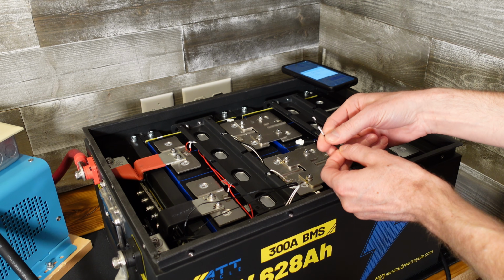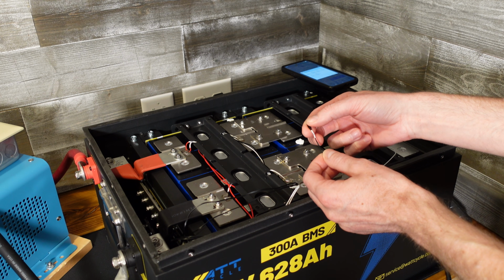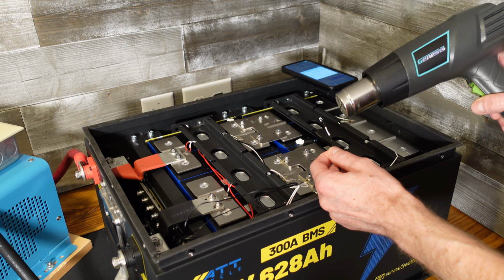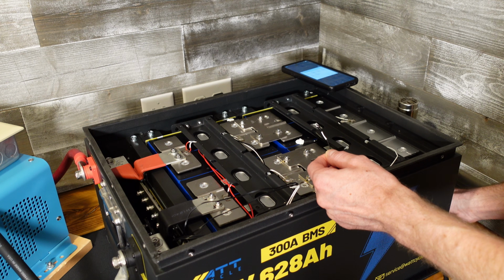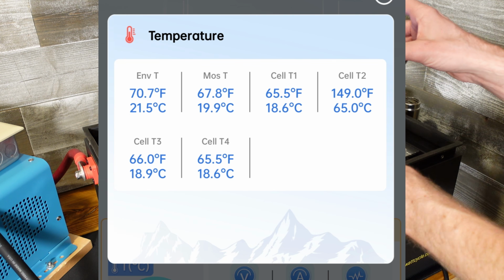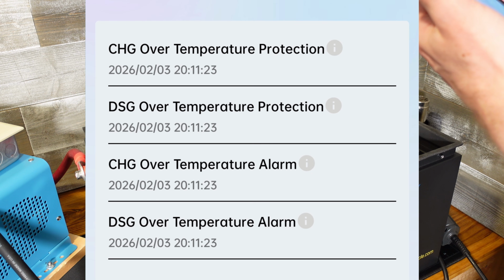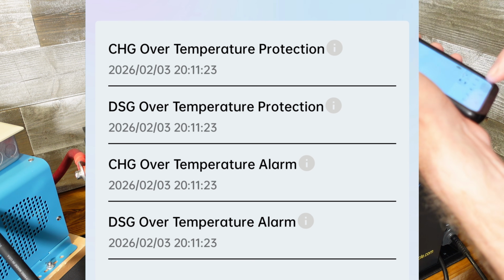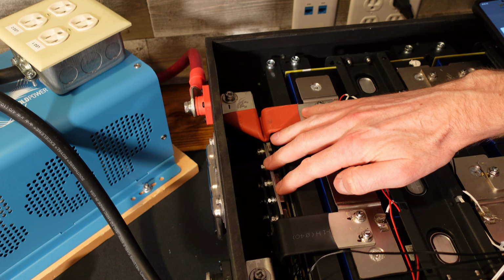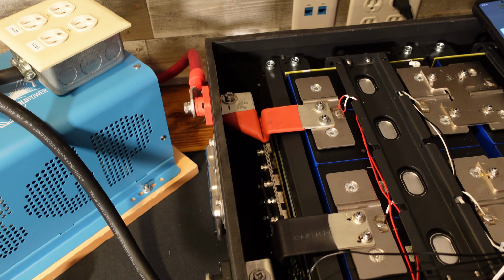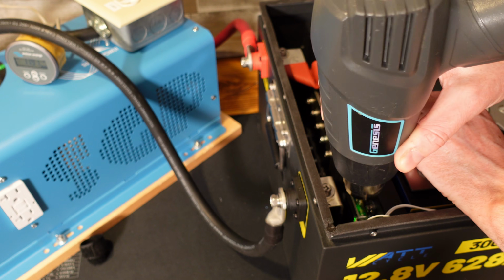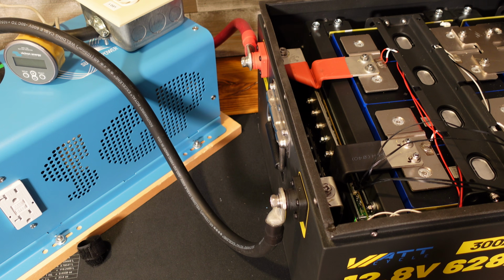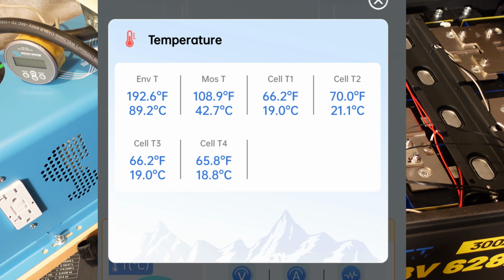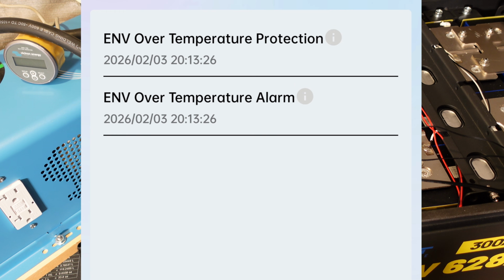I've got one of the battery sensors pulled off. This is T2 specifically. All right, and it did shut down. We're at 153 degrees there. So the alerts we got are charge and discharge over temp protection and charge and discharge over temp alarm. Next, I'll aim the heat gun down on the BMS here and see if we can get the environmental sensor to trip. All right, it shut down right around 197. The alerts are ENV over temp protection and ENV over temp alarm.